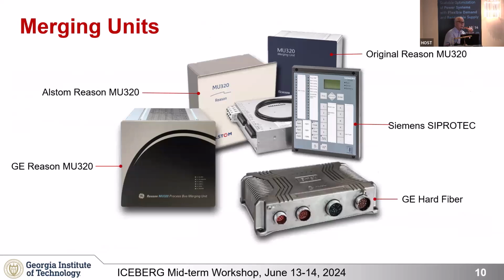And then another thing happened. As a matter of fact, at Georgia Tech, my group was instrumental in that. We said, well, if we look at the protection and control system, every relay has its own data acquisition system and so on. Do you know how much duplication this is in the system? Okay. We have many data acquisition units embedded in every relay. Okay. So why don't we separate this? Just have a data acquisition separate from all the applications we do, whether it is protection, control, operation, optimization, and so on. And that gave rise to the merging unit.